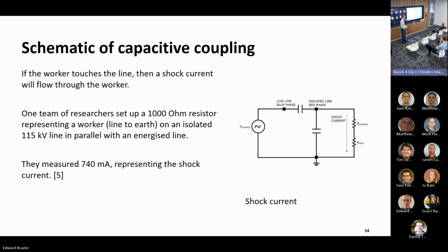So to put that in perspective, that represents the shock current through the worker. An RCD will trip at 30 milliamps to prevent a fatality if there's a shock. This is 740 milliamps, so it's definitely hazardous.